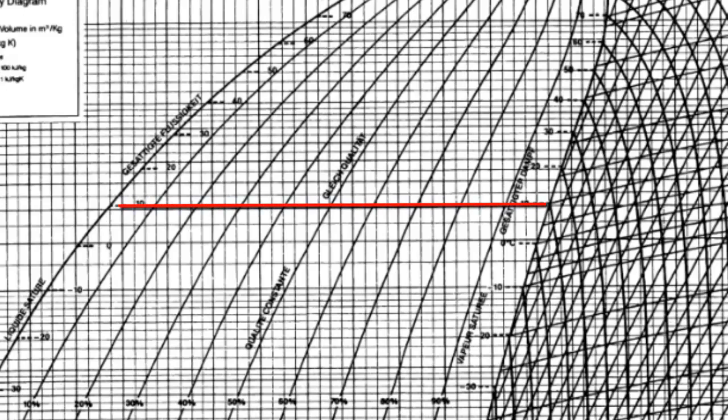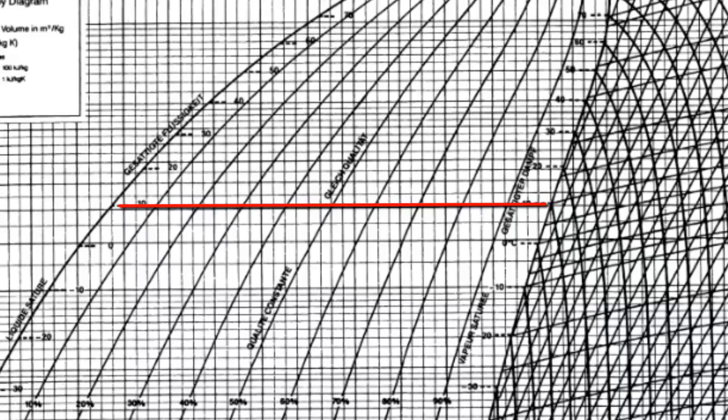So, we will use the low pressure or the evaporator temperature to draw a horizontal line. As we see on this chart, the evaporator temperature was given as 10 degrees C. And therefore, we have drawn a horizontal line that connects the 10 degrees C, both on the left-hand side and the right-hand side under this bell-shaped curve. And we have the lower part of the cycle.